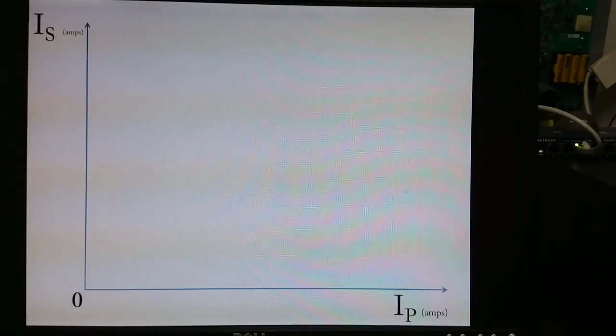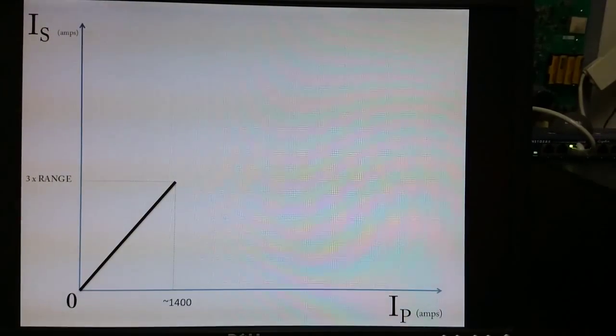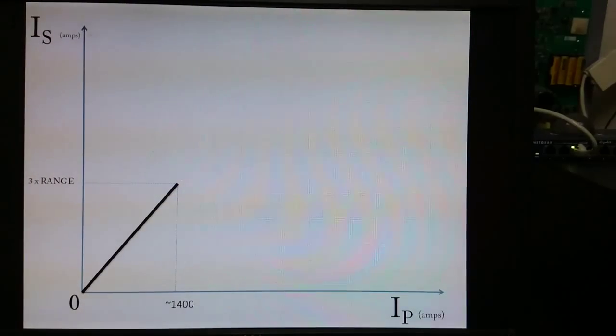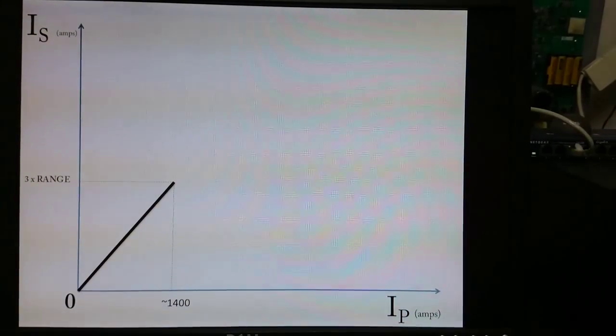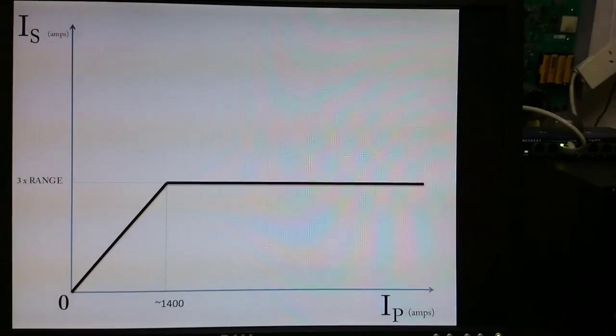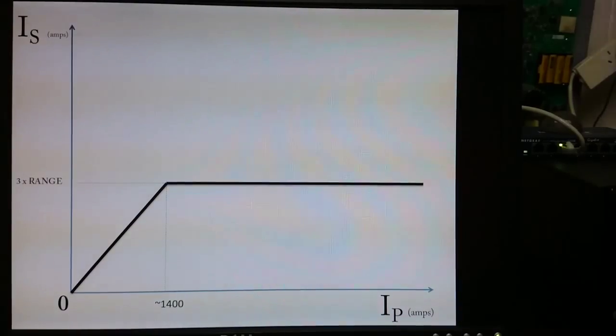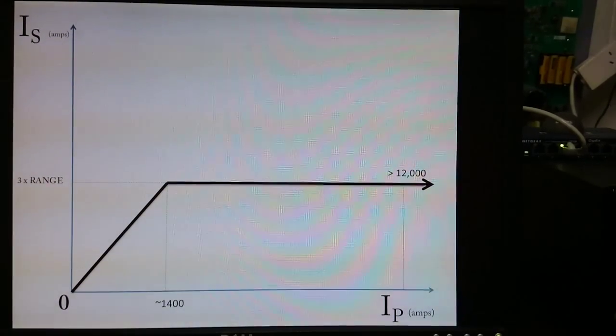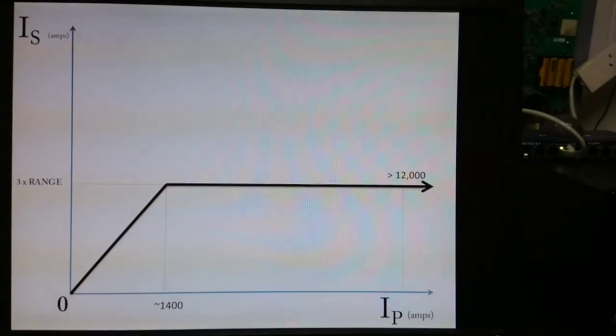The CT used in the NGK switch has attributes of both metering and protection. The output is linear at up to three times the rated switch current, and more importantly, its saturation characteristics are such that the output current remains usable at up to thirty times the measurement range.